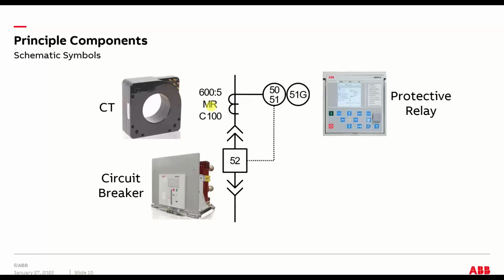And the 5 goes back again to the fact that they were electromechanical relays, which drew physical load off the CT. So standardizing on 5 amp gave them a little more power capacity, so they could drive the actual elements that make up the relay. That's just a little background. And this last number is an accuracy class for the CT.